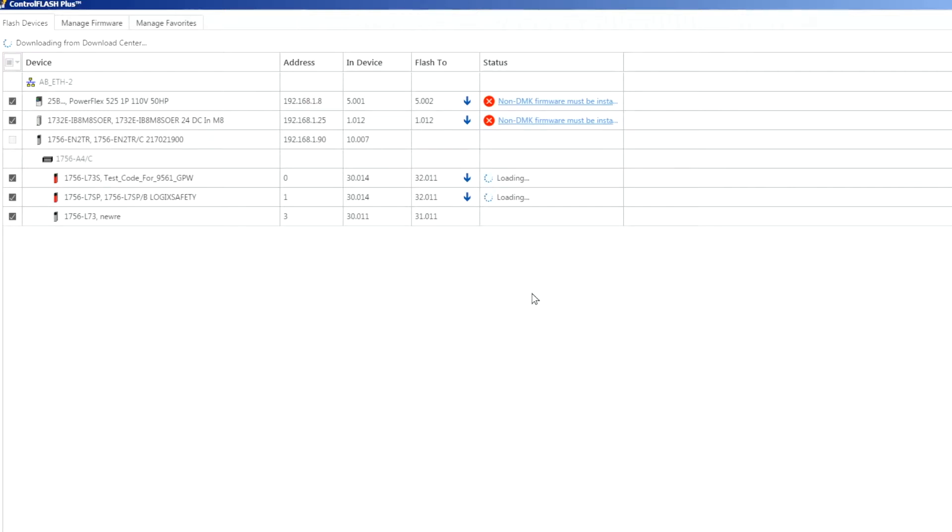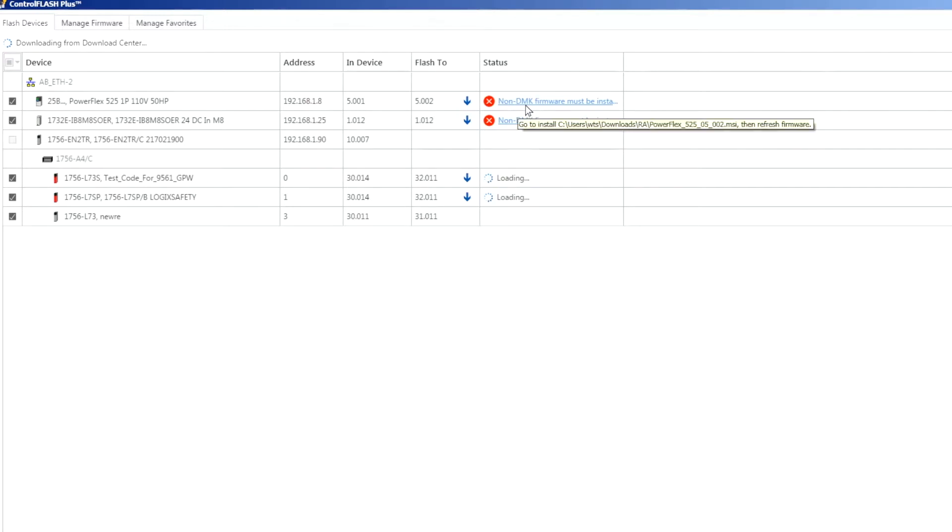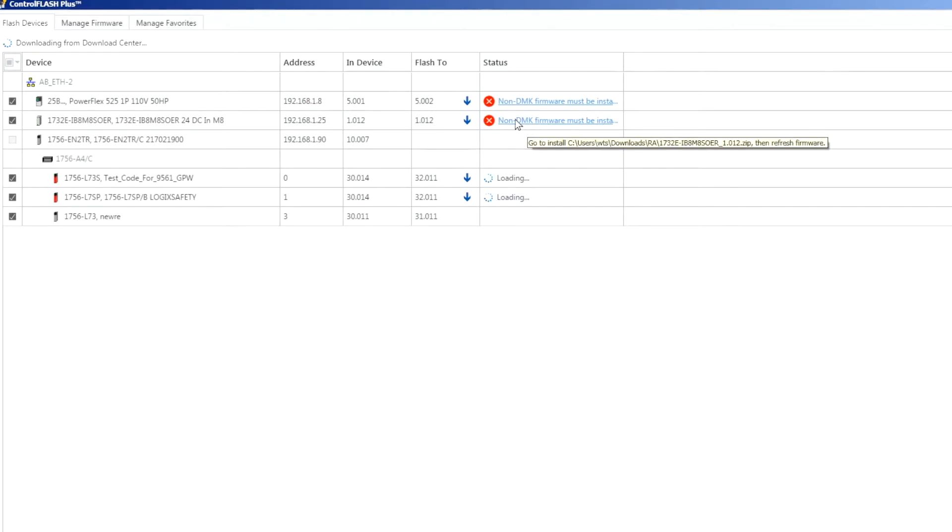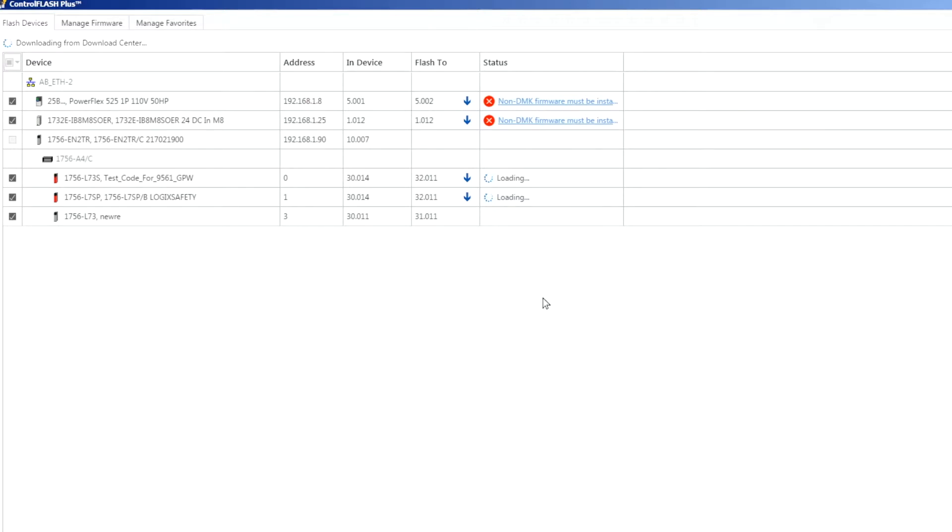We'll let that keep running through. Looks like I had a couple of errors on this one. The reason for these is that they're not in the DMK file format and that's what ControlFlash Plus uses, so it's telling me to go to the install directory where it downloaded the zip file, install that firmware file manually, and then come back through and run it. In this instance I'll just leave those be for now since I didn't have those downloaded and installed ahead of time and I'll wait until these finish up and then we'll run through the flashing.